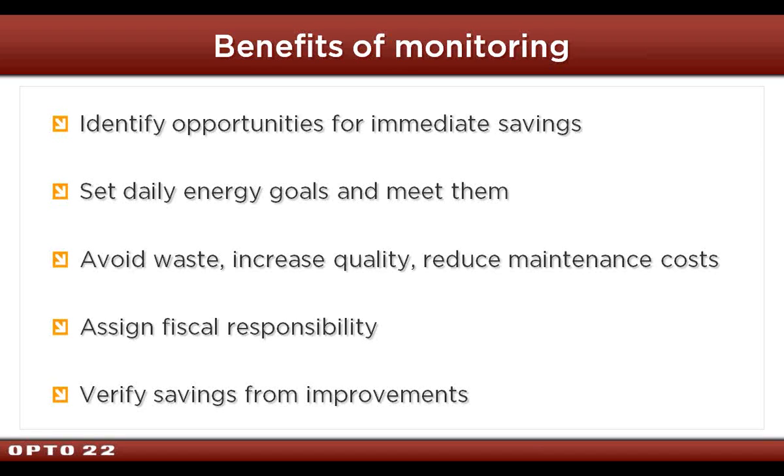So the benefits from monitoring, you get those immediate savings. We started creating them the first day. Stuff that's on that shouldn't be. You look at your meters. Can you account for where everything's going? We ran buildings for people under contract for years, and I estimate we spent 30% of our time undoing today what someone had screwed up since we were in there yesterday.